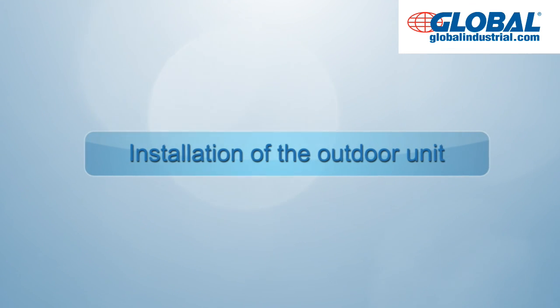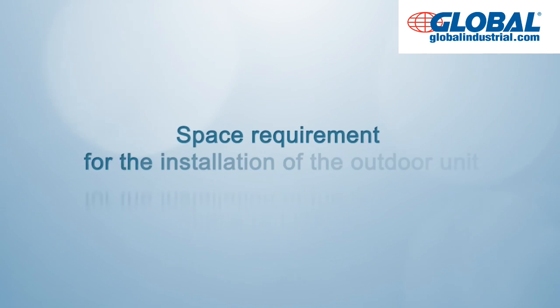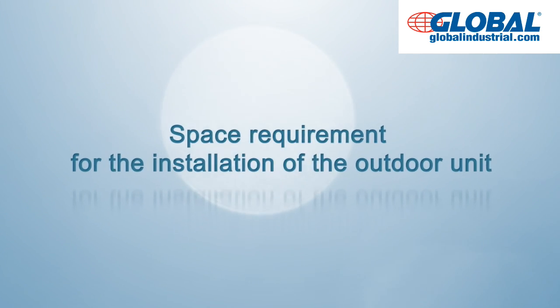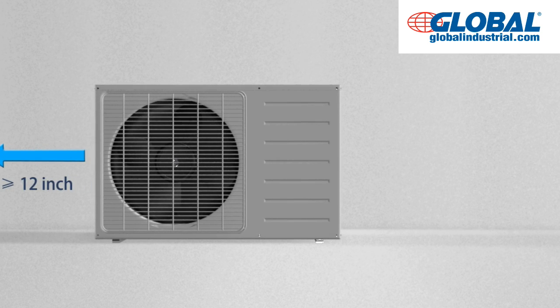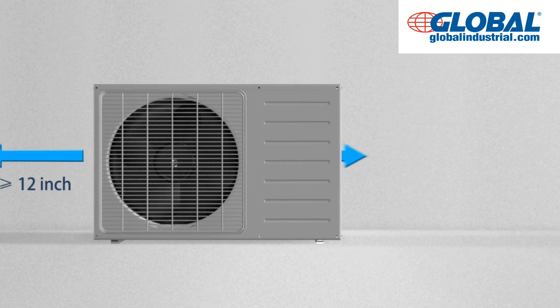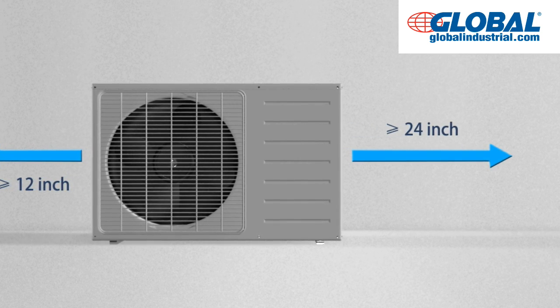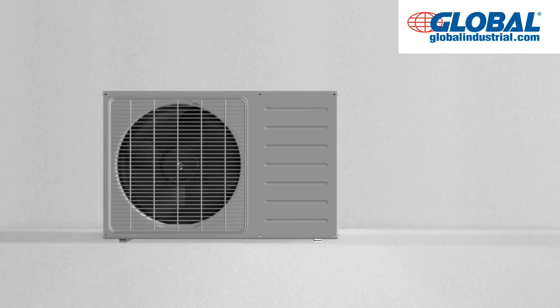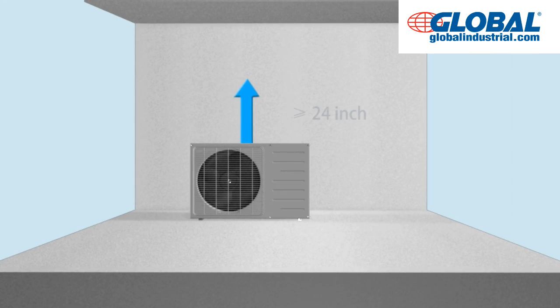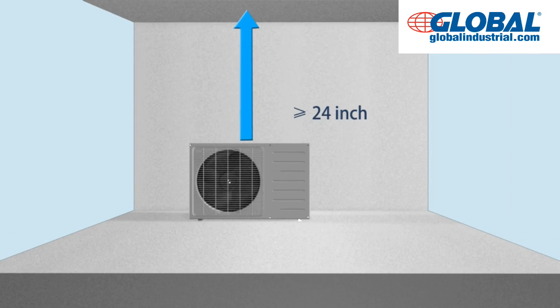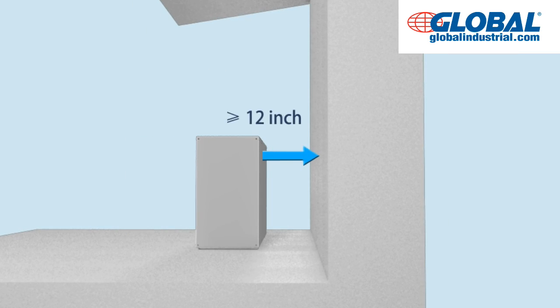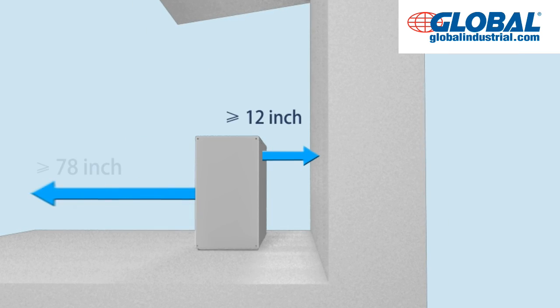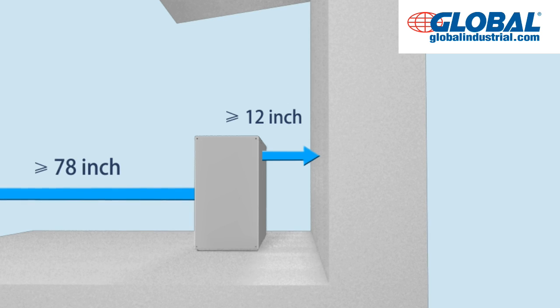Installation of the outdoor unit. Space requirements: no less than 12 inches for left space, no less than 24 inches for right space, no less than 24 inches for upper space, no less than 12 inches for back space, and no less than 78 inches for front space.